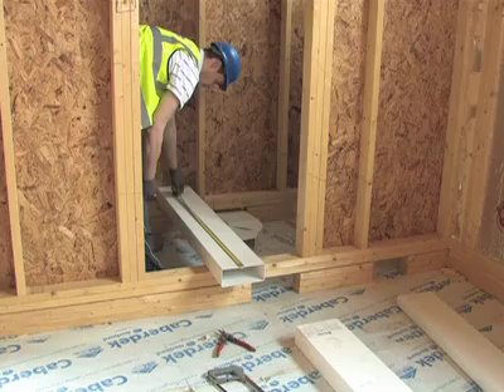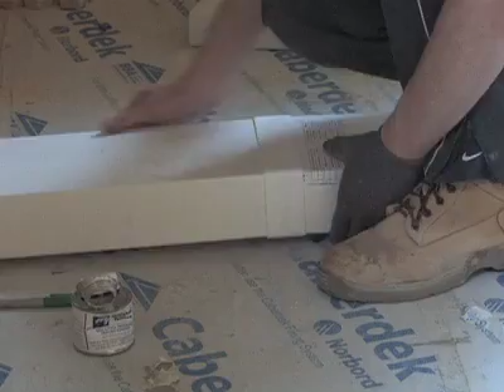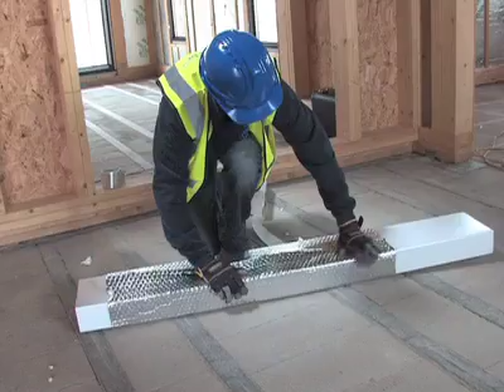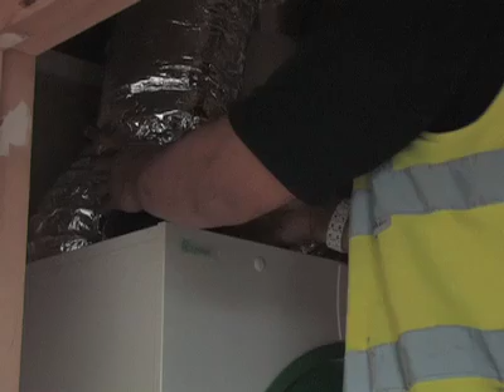Seal all the duct joints properly with a flexible silicone sealant to protect against leaks and support them to avoid strain and failure at a later date. All ducts passing through unheated spaces and the 2 ducts to atmosphere must be insulated to prevent condensation and preserve heat. Use flexible ducts only for the final connections.